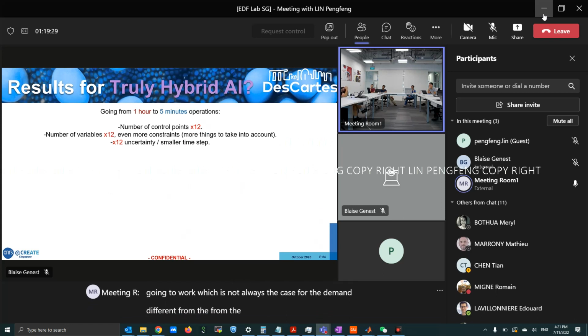The second thing, it needs also to be compatible with the statism, like for generation. It cannot be just from 0 to 1; it has to be compatible with the statism as well. And that means you have to implement it, which means implementing some kind of droop control on the load, which is not as easy as putting it on the generator.